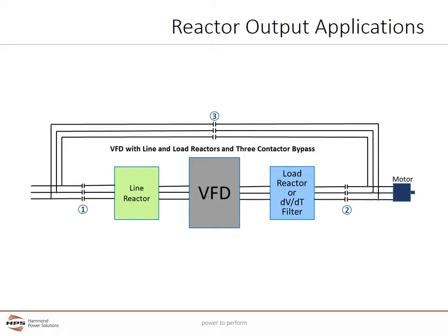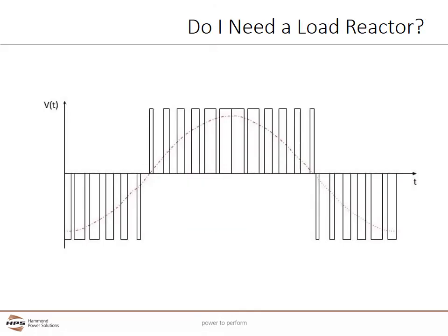Now let's discuss the benefits of load reactors between the VFD and the motor. Load reactors are found in the output of a VFD between the VFD and the motor. HPS Centurion line reactors are designed so the same line reactor can be used on either the load or line side of the VFD without any derating. By varying the width of DC pulses on the output of a VFD, a VFD simulates a wide range of frequencies to control motor speed. This PWM wave can cause problems with cabling and the motor—the motor runs hotter, sounds louder, and there is often a high-pitched whine.